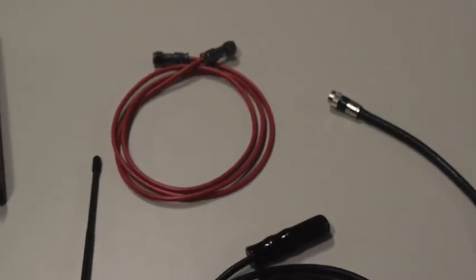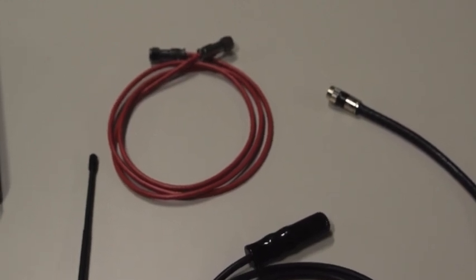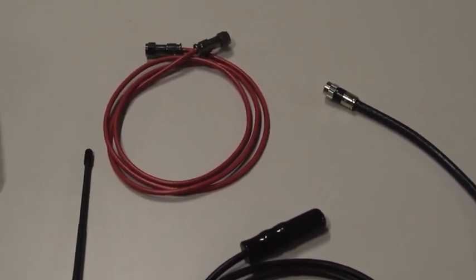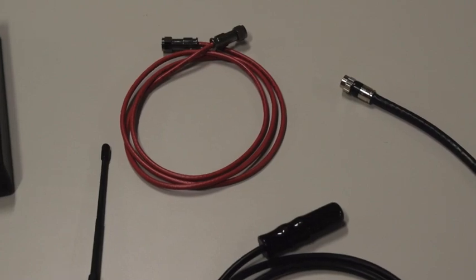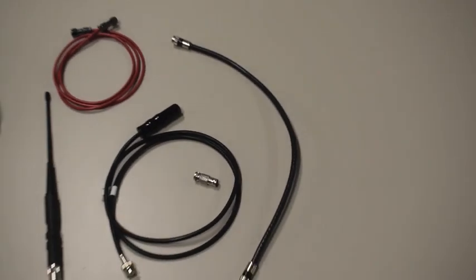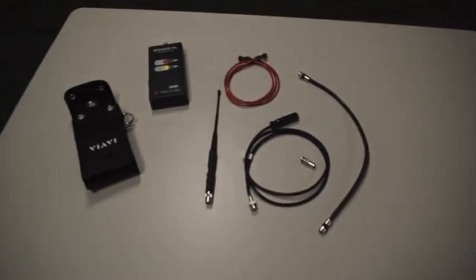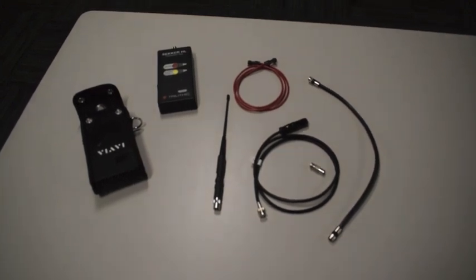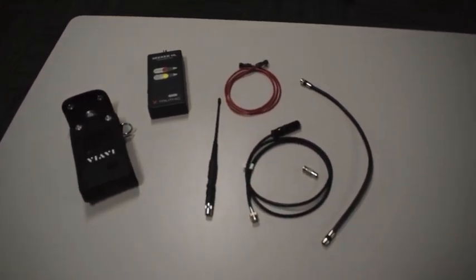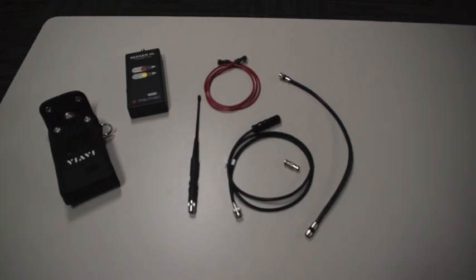This red jumper was included by mistake. That should be discarded, as that will actually cause more leakage than it will help you fix it. So we've gone ahead and made our own jumper for this. As part of this kit, we're going to put the transmitter inside the case and we're going to carry around the rubber duck and near field probe.